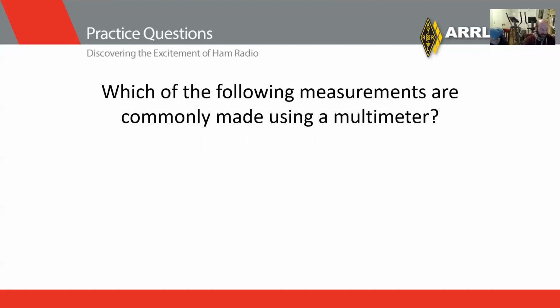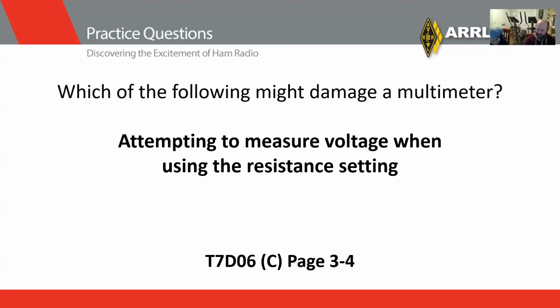Did they mention you'll see a change in resistance if you hook up a meter to a circuit with a capacitor that has a residual charge? Yes, it essentially powers the circuit at that point. If you have a high capacity capacitor, it will discharge through the circuit when you put the meter on there, and you'll see the resistance start to change and increase. You have to wait till it fully stabilizes before you get the true reading.